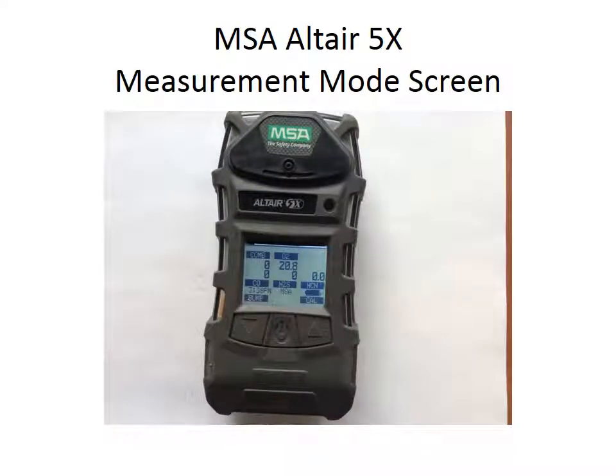The measurement mode screen: once it's gone through that fresh air setup, it goes into measurement mode, and this is the screen you'll see when you're ready to actually take samples of the environment. Just to point out on the screen, it has the time on there. At the bottom, you'll see the bump and the calibration flags. Those respond to the down arrow and the up arrow. If you press those arrows, that's what's going to put you into the bump or the cal.